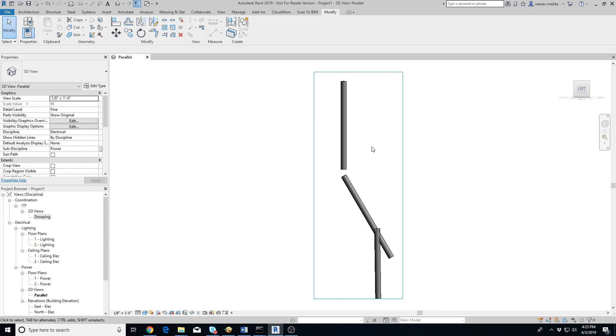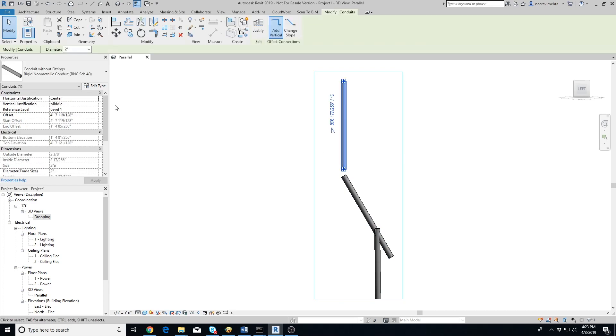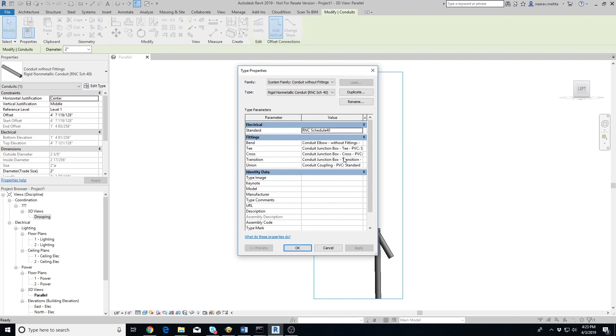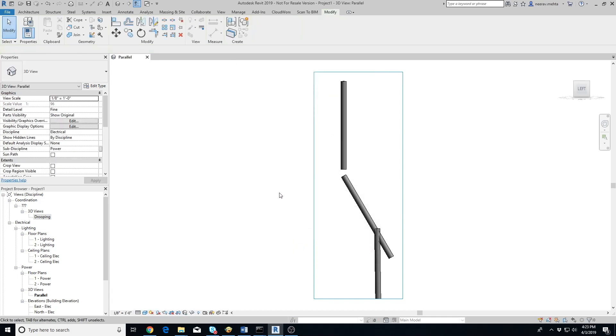As shown in the video, we are not able to connect the two conduits using the Trim/Extend to Corner tool. To connect the two extracted conduits you will need to use the Align and Connect tool provided in the Scan to BIM add-in. But before that, make sure that the conduit elbows and transitions are already loaded — you can verify this by selecting a conduit, clicking Edit Type, and confirming that elbow and transition fittings are defined.